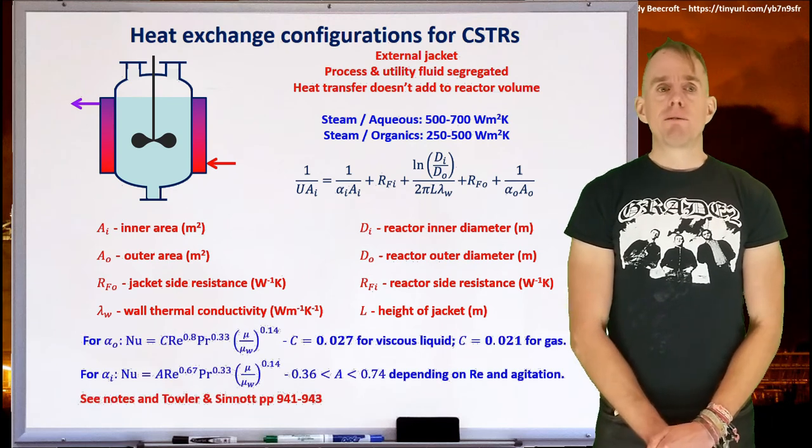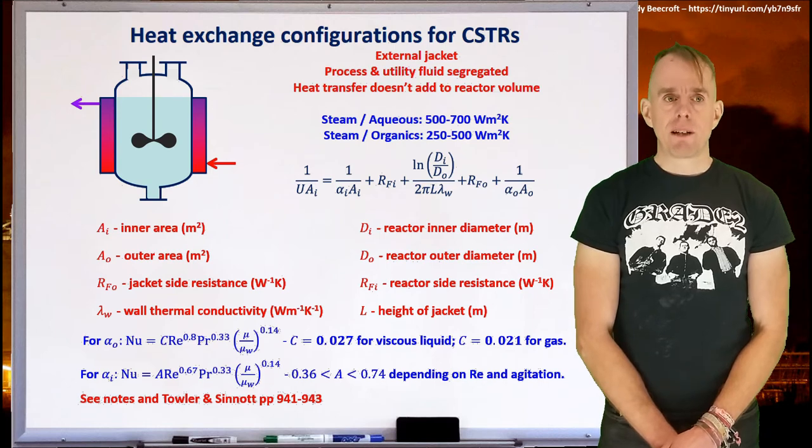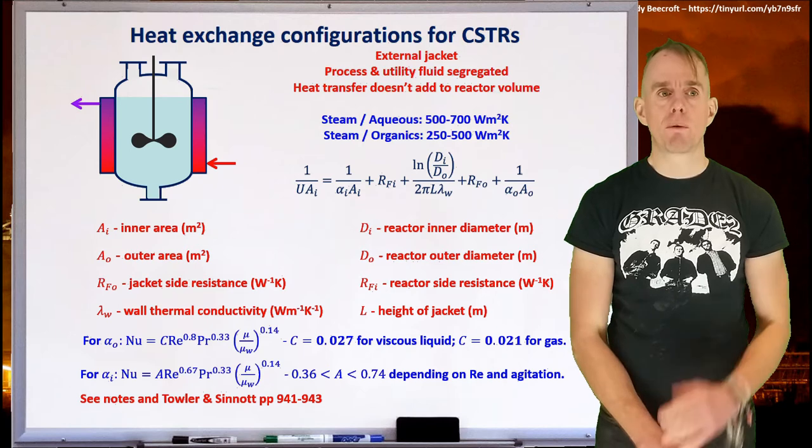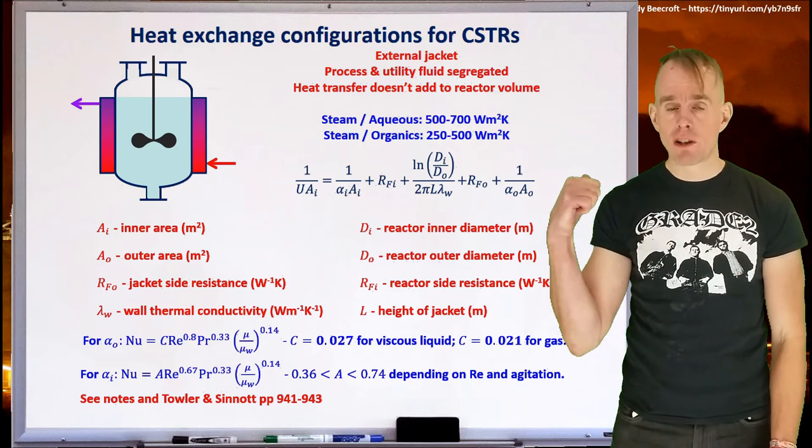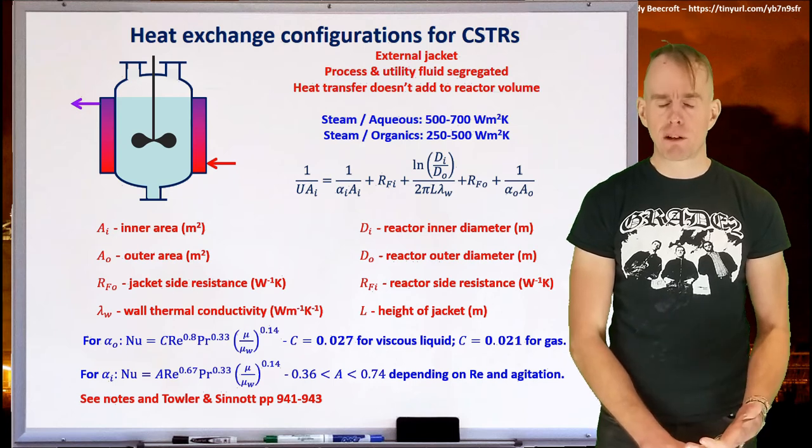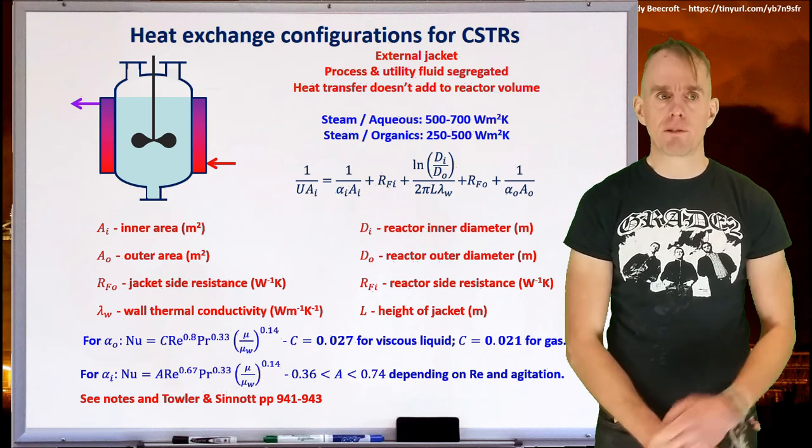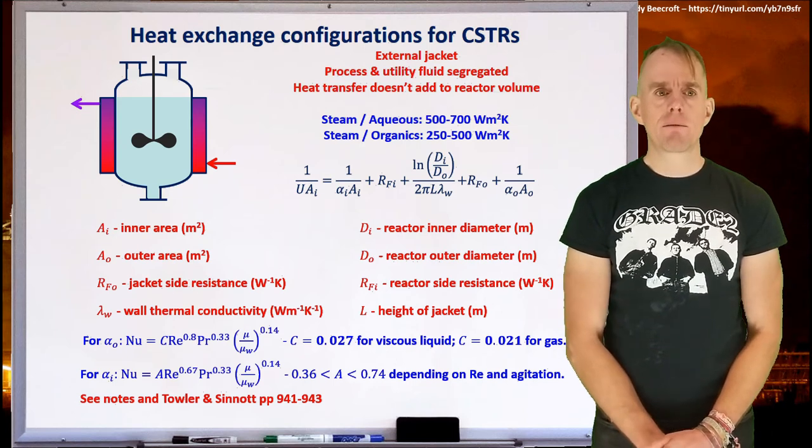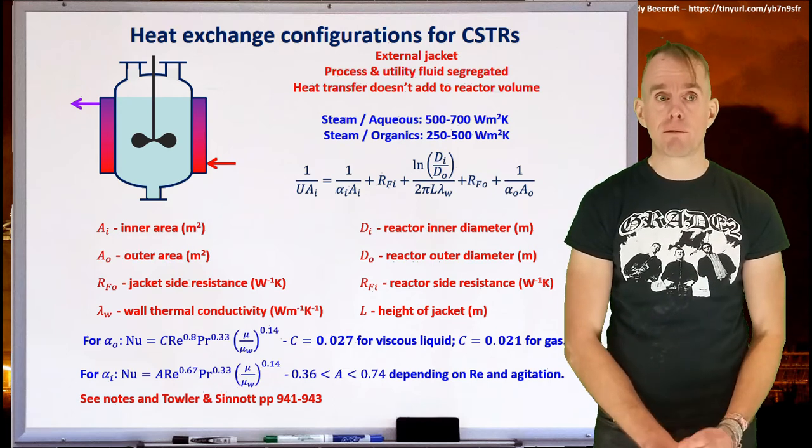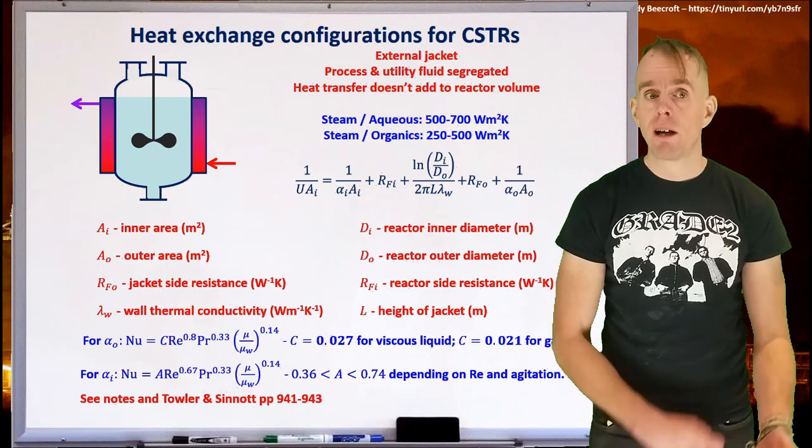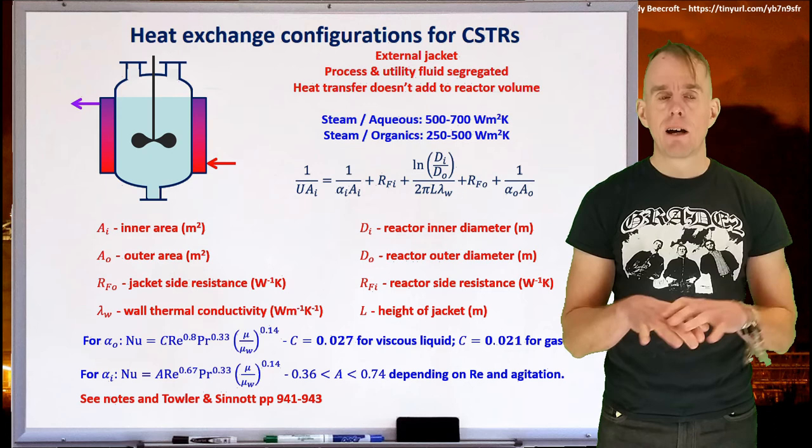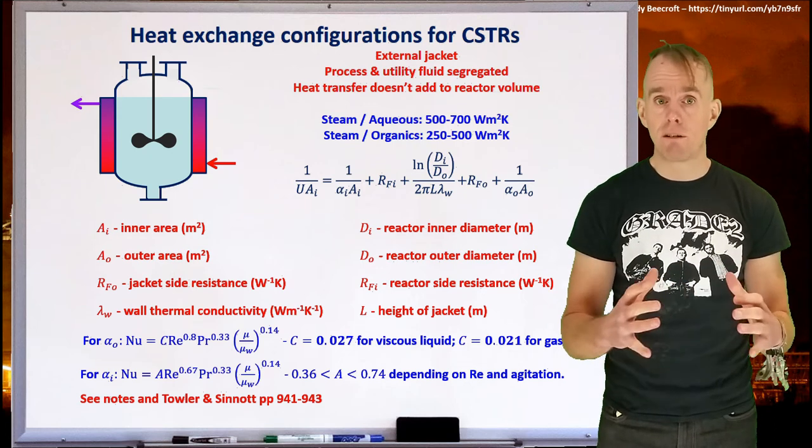Now, there are various correlations you can use to find out what your film heat transfer coefficients are. So for example, for viscous liquids, there's a correlation here, a Nusselt number correlation, that gives you your film heat transfer coefficient, which is alpha zero. And you'll find that the constants in this depend on the type of reacting medium you've got, varying from 0.027 for a viscous liquid to 0.021 for a gas. So relatively easy to get a rough approximation because C doesn't vary a great deal.